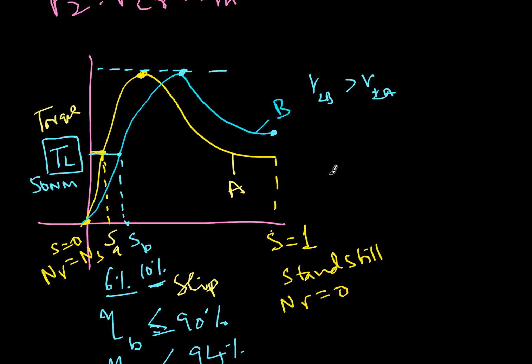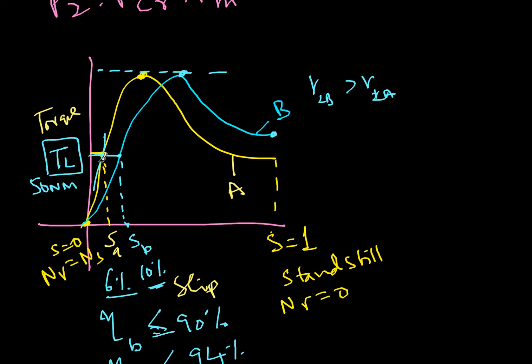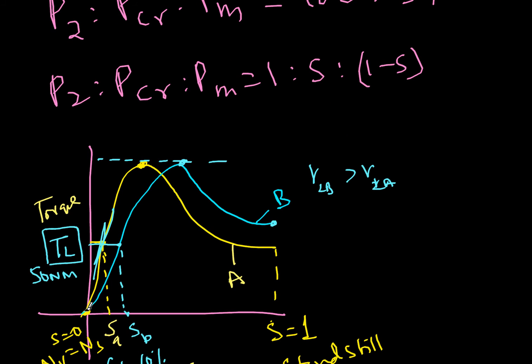So the machine should be designed such that the slope here is very steep. In that case, you can supply a wide variety of torques with very little variation in the slip, and very little amount of losses. So an efficient induction motor will have a steep curve here, starting like this. But what is the disadvantage? Whenever this part is steep, when it comes down, the starting torque will be lesser. Whereas if this part is slightly less steep, the starting torque might be more.